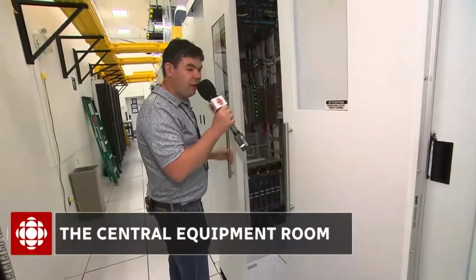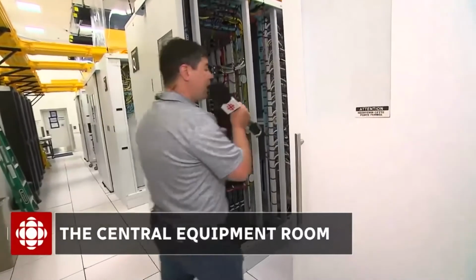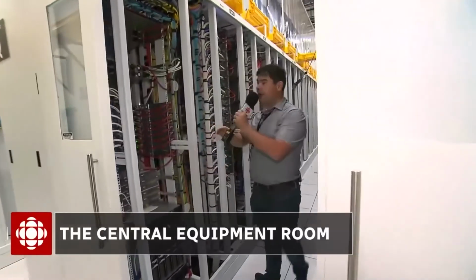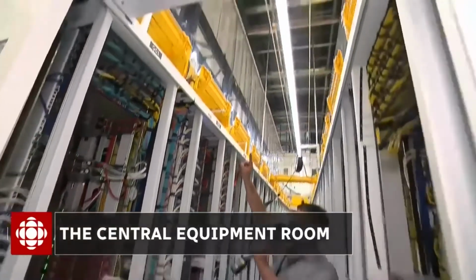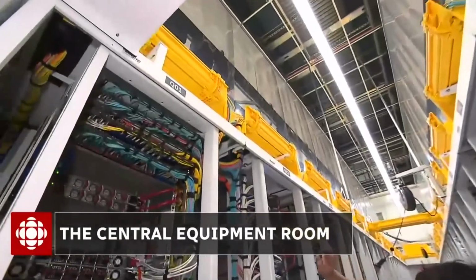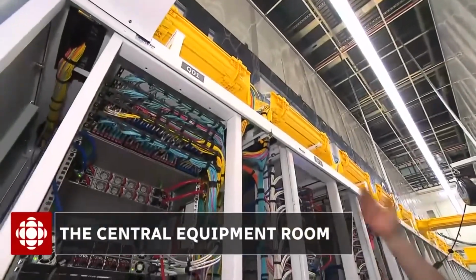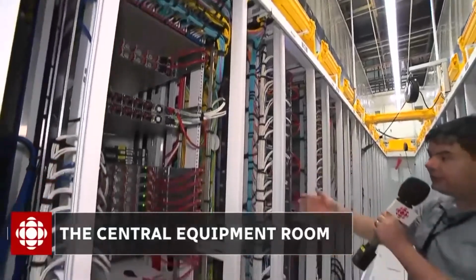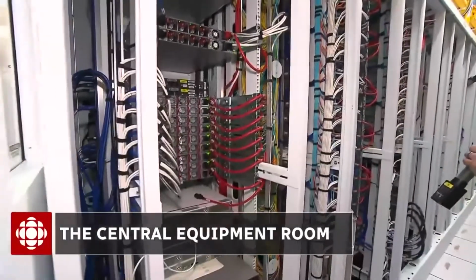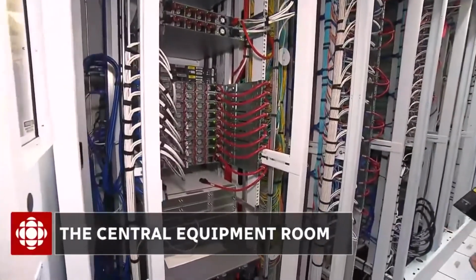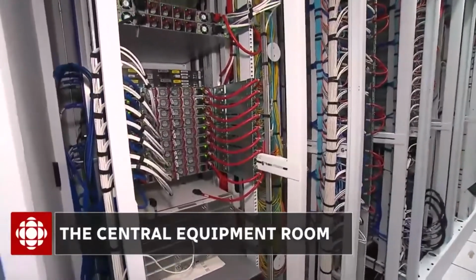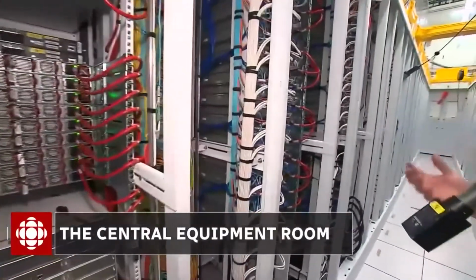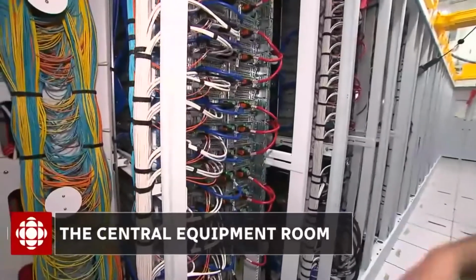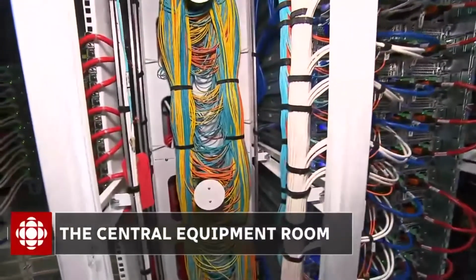The wiring strategy is that every delicate fiber is run from above the rack, so we can see the fiber trays. Then it goes into that fiber management system to the equipment. We need a fiber management system because cut-to-length fiber is very expensive, so in order to use standard cable lengths, we need a slack management system.